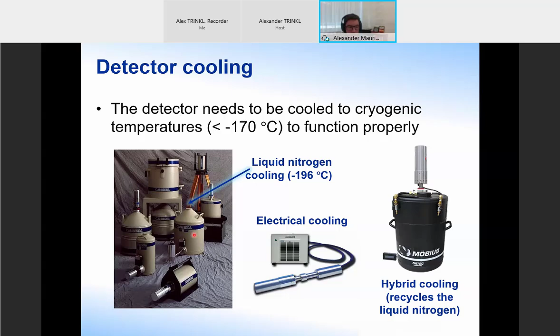If we look at the anatomy of a nitrogen cooled detector, a cross-sectional view might look something like this. You have your detector crystal mounted inside the end cap, usually connected to some kind of preamplifier, and the whole thing has a long cooling rod with a cold finger at the end, which is used to keep it cold by keeping it in contact with the liquid nitrogen inside this dewar here. That's basically how the main setup might look. If you have a typical traditional nitrogen cooled detector, chances are it looks quite similar to this.